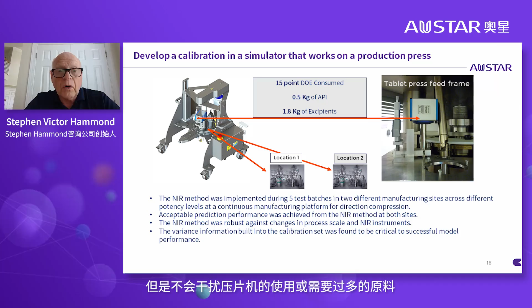So what was done was a 15-point DOE using the simulator, and various blends were made with the ingredients from both locations and data collected to make a calibration with the intent of working on both tablet presses. The DOE consumed only 0.5 kilograms of API and only 1.8 kilograms of the excipients. So this is a very material-sparing approach for making near-infrared models that are very effective but not interfering with the use of the tablet press or requiring excessive amounts of material.